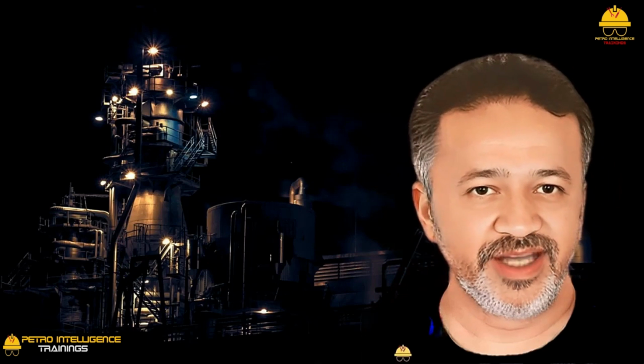A fixed tube sheet exchanger in a refinery precondenser service for a vacuum tower is a throwaway item. One operator just engaged in this exercise. Replacement for the 60 inches ID shell, as per specs above, was $1,300,000 in 2013. Not a happy situation.